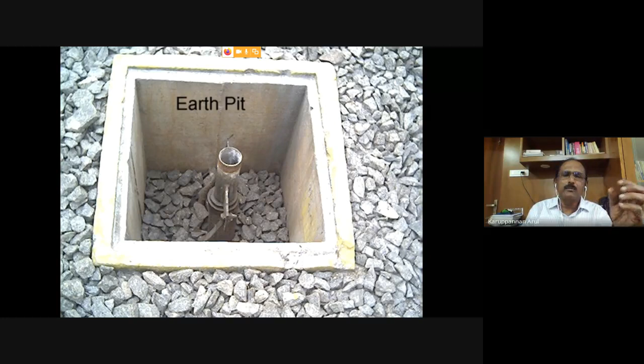This earth resistance should be measured by an equipment called a Megger, and the Megger reading should not be more than 5 ohm in any case. If it is well within 5 ohm, then the earthing is proper. So we should ensure that earth resistance is below 5 ohm for effective conduction of electricity to the earth.